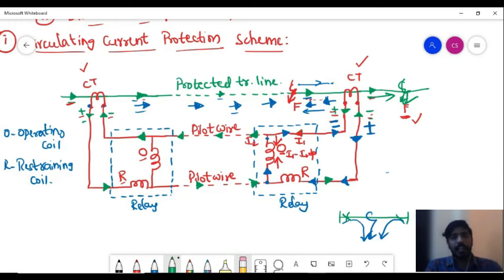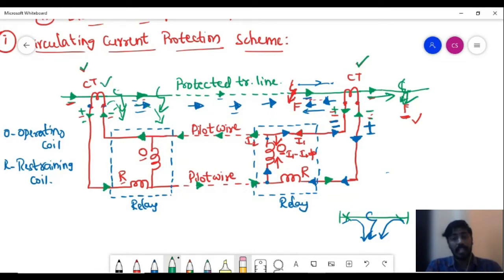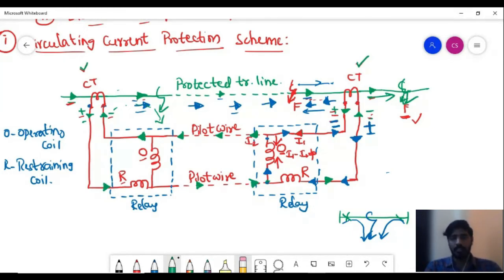The polarities of the CT at the receiving end are reversed only when the fault is on the protected line; the sending end CT polarities are not reversed. If the fault is anywhere on this protected line, the direction of the fault current with respect to the receiving end CT is reversed. Now during the fault, the current flows not only through the restraining coil but also through the operating coil. Both the restraining coil and the operating coil are now energized, and therefore the relay will operate.